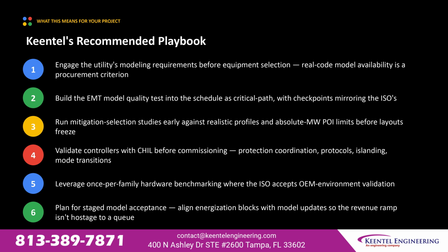Here's Keentel's recommended playbook. 1. Engage the utilities modeling requirements before equipment selection. Real code model availability is now a procurement criterion. 2. Build the EMT model quality test into the schedule as critical path with checkpoints that mirror the ISO's. 3. Run mitigation selection studies early against realistic profiles and absolute megawatt point of interconnection limits before layouts freeze.